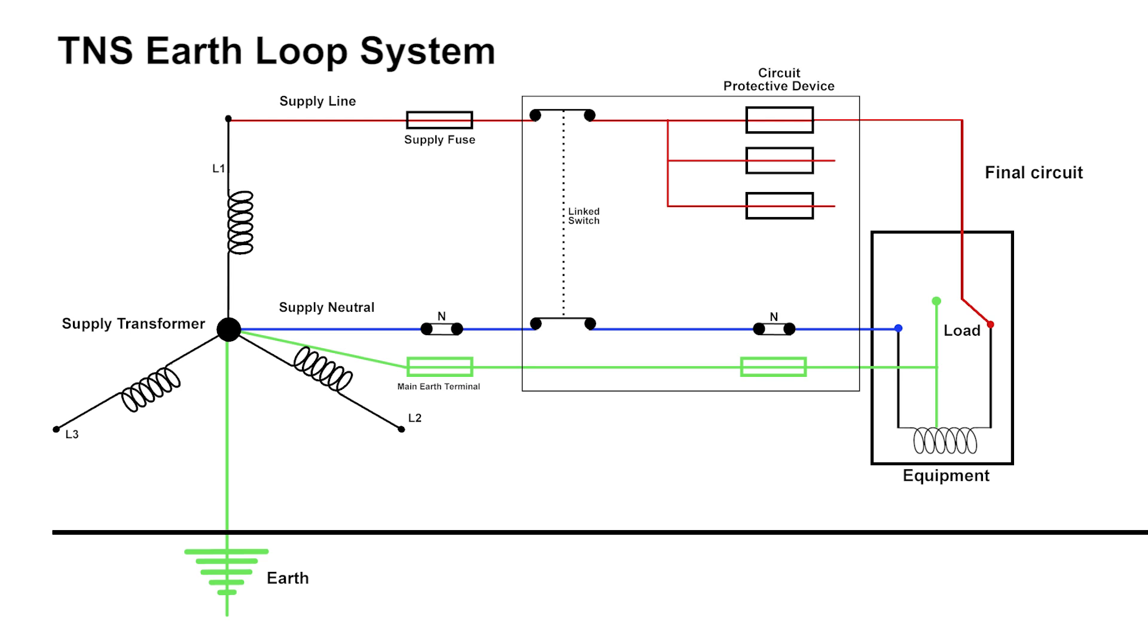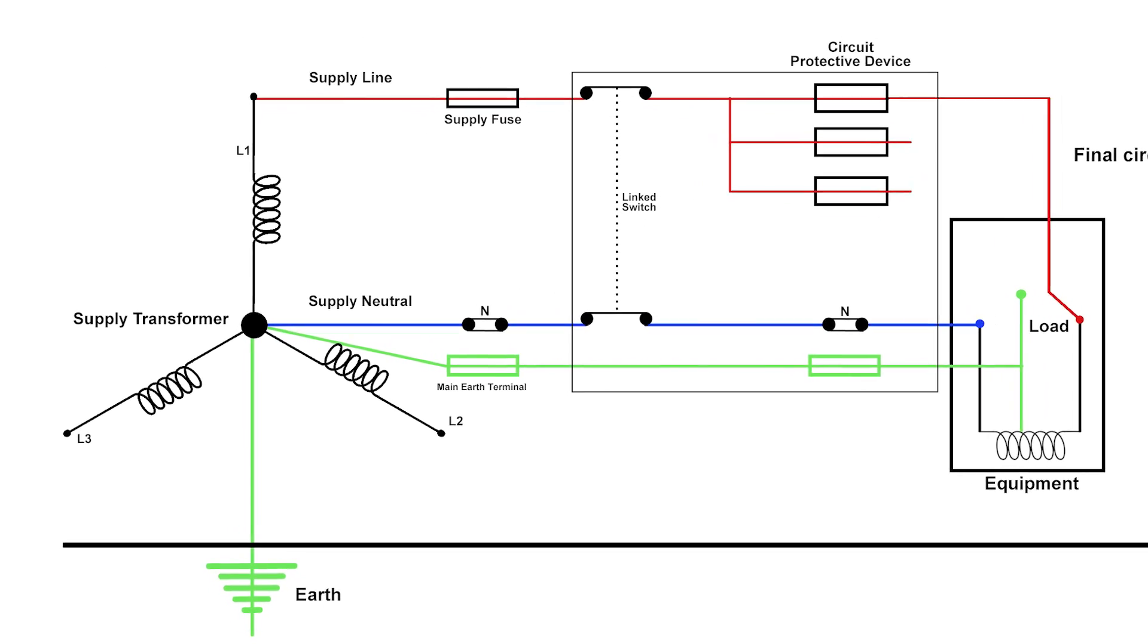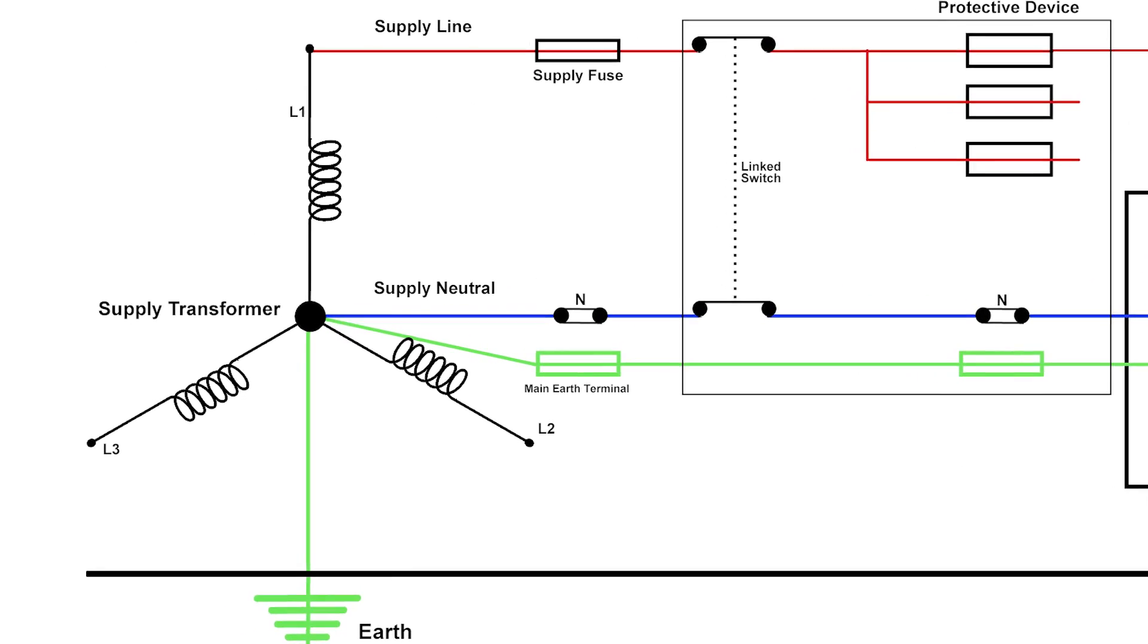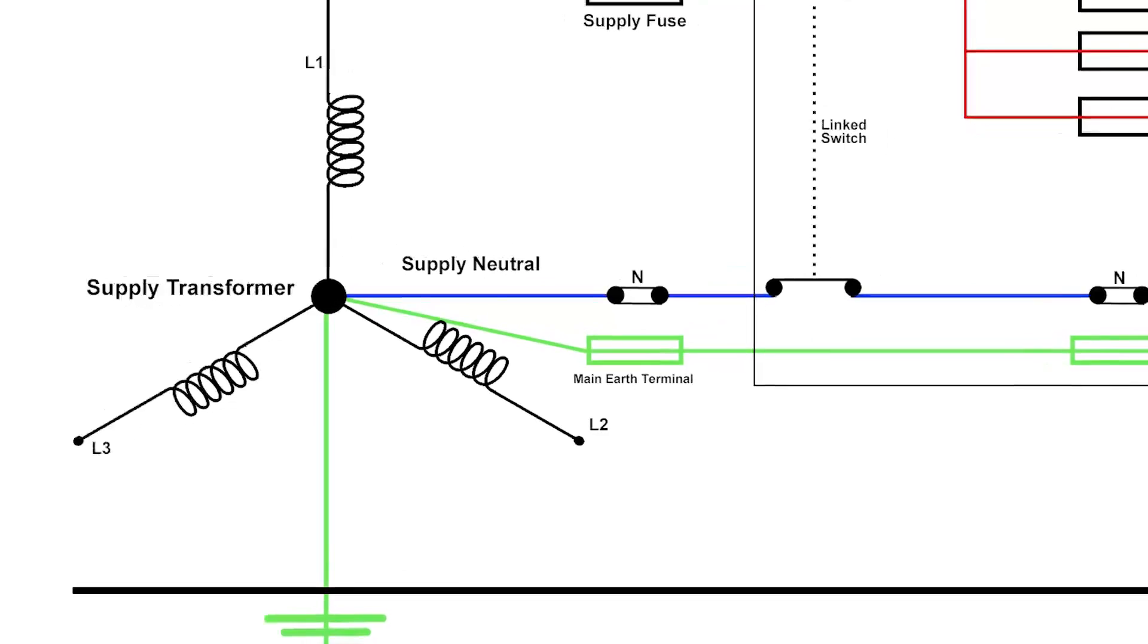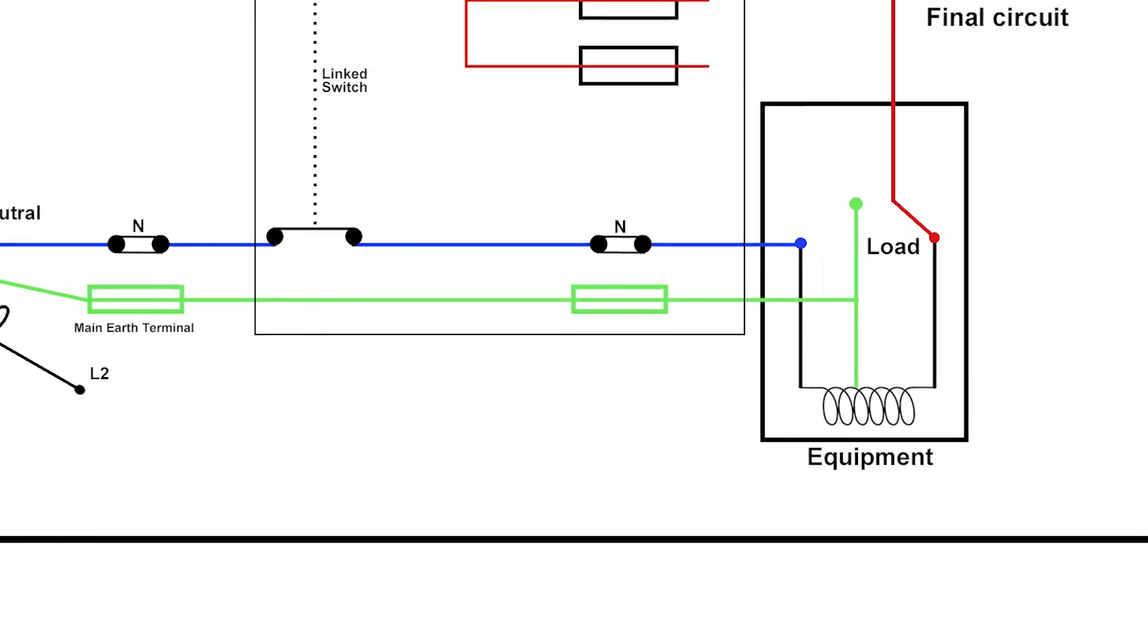The drawing we're looking at is just a diagram of a TNS system. When we talk about earthing systems, the T would always stand for earth. N in this case is neutral, and S means that the neutral and the earth are entirely separate throughout the whole of the installation. In other words, they're separate from the supply transformer right through to the final circuit.